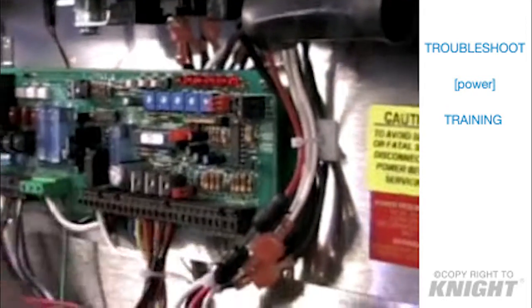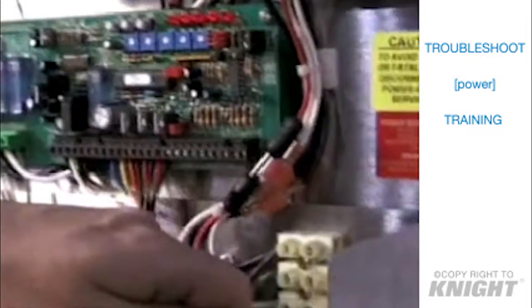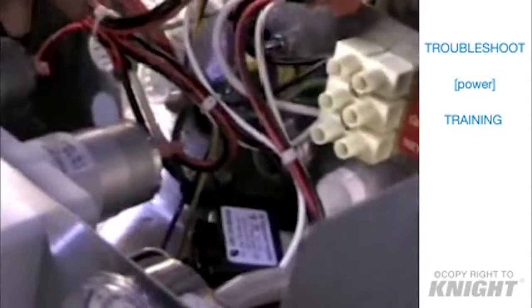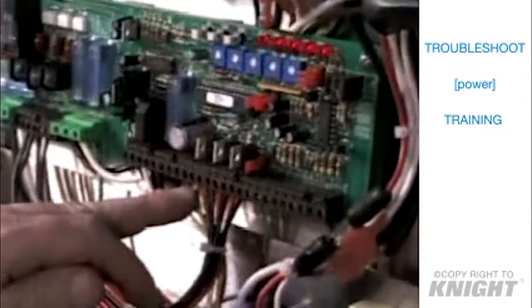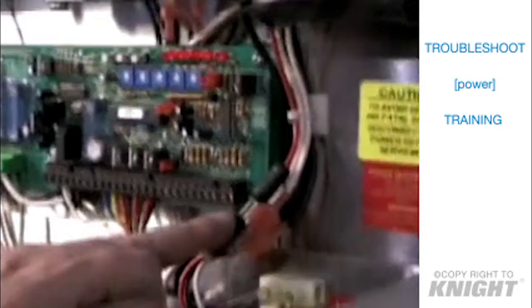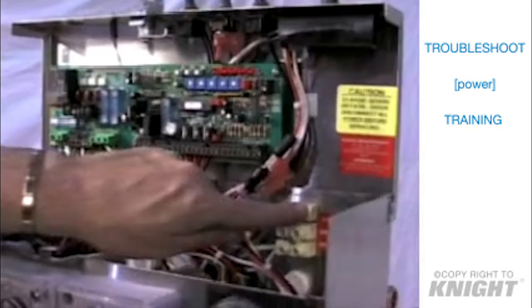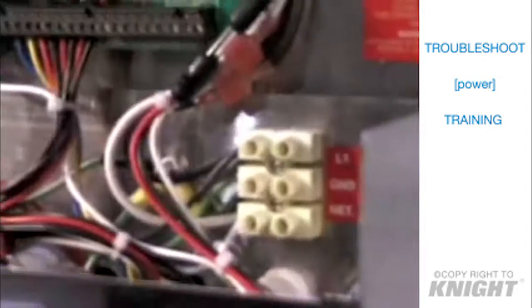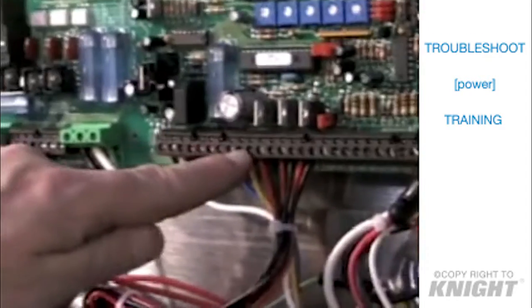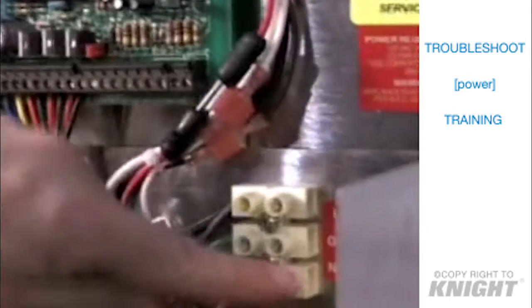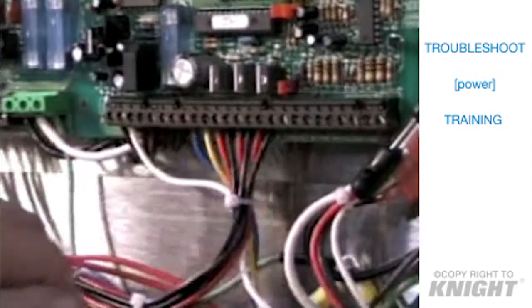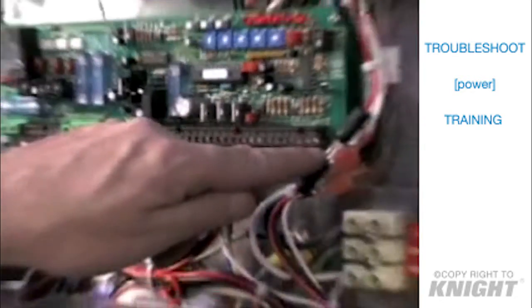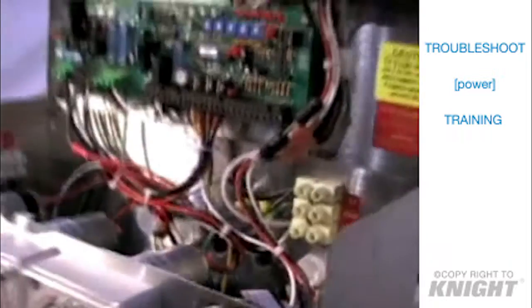here. If this fuse blows, there'll be no power to the transformer, therefore there'll be no power to the board, therefore the machine won't operate. So this fuse plays an important role, because if it doesn't work, the whole machine won't work. You can check here to make sure you've got power here, and then you can go here and check if you've got power here. And if you've got power here and don't have power here, then your problem has got to be either the fuse or the transformer. 99 times out of 100, the problem's going to be the fuse.